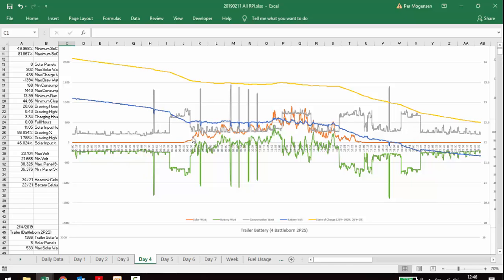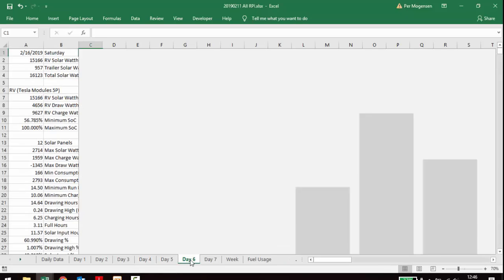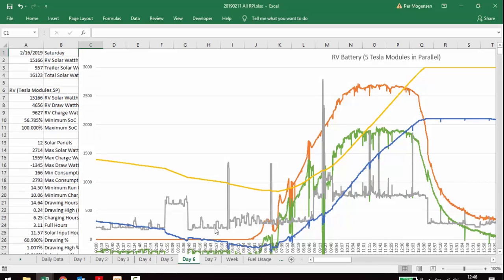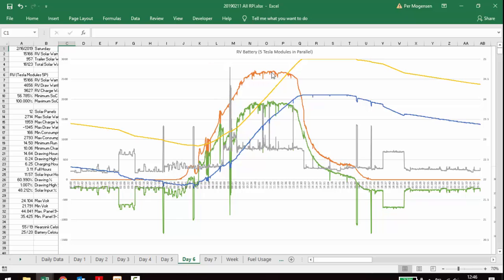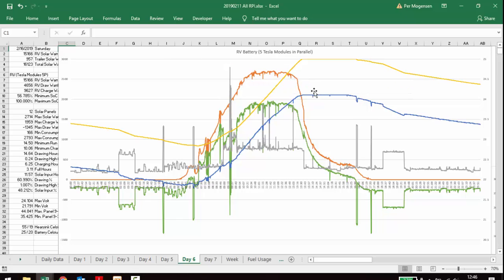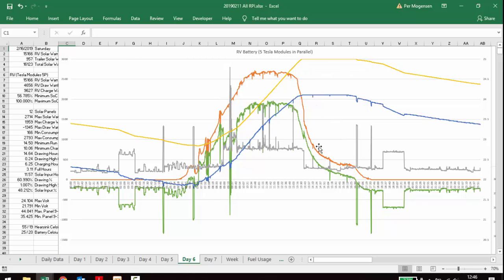The orange is the input of the sun, so this one is a pretty low day. But if we actually go to Saturday, the day where it actually ends up being fully charged, we can see the voltage grows and then flat lines at the top where we can't really output much more or accumulate more. And here we would have had more energy, but the batteries end up being 100% charged and basically this tapering off because we can't use it.